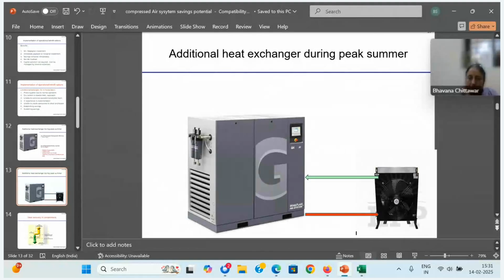As well as, you can demand a new compressor to be like that. You order a new compressor, you ask them, I want water cooled with the extended radiator. There are a lot of suppliers in the market for extended radiators. This will cost much less than air cooled. Your performance and your room size also will be less. You can keep the radiator outside. No water is required, the one time filling of water is sufficient. Unless water is leaking, it will run for almost a year. After a year, you can just check or replace the water. Okay. So this is a good opportunity available for any vendor, any client.